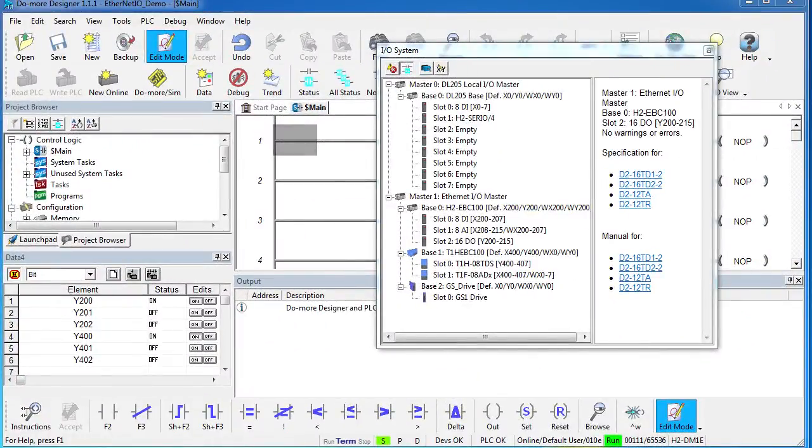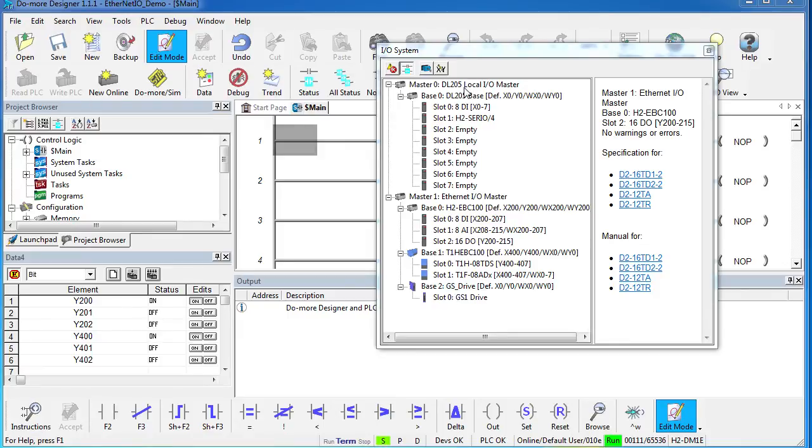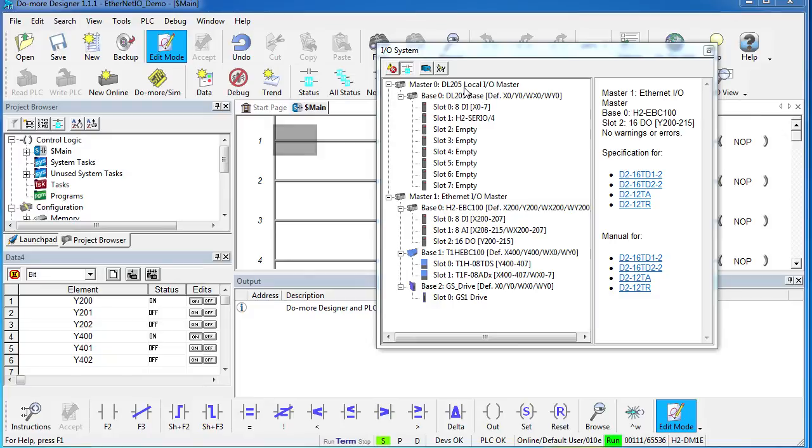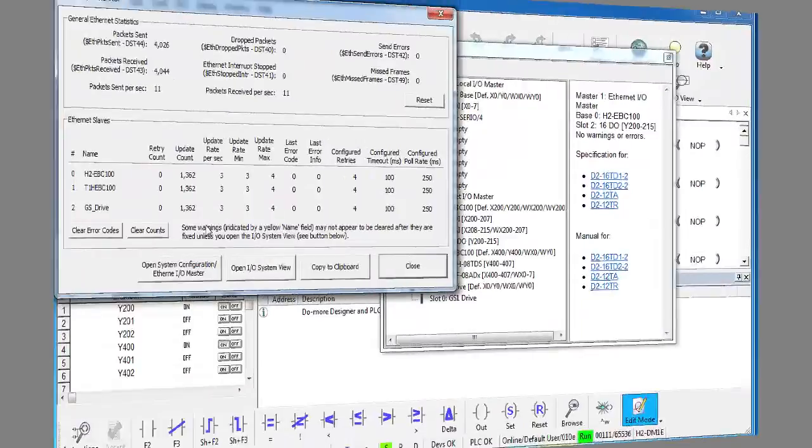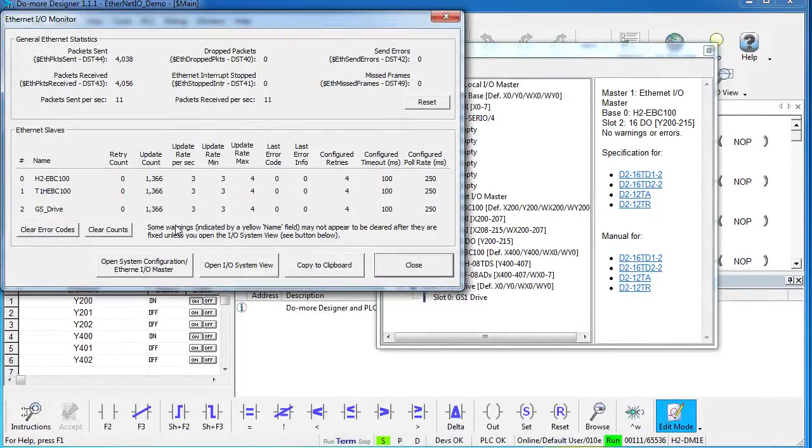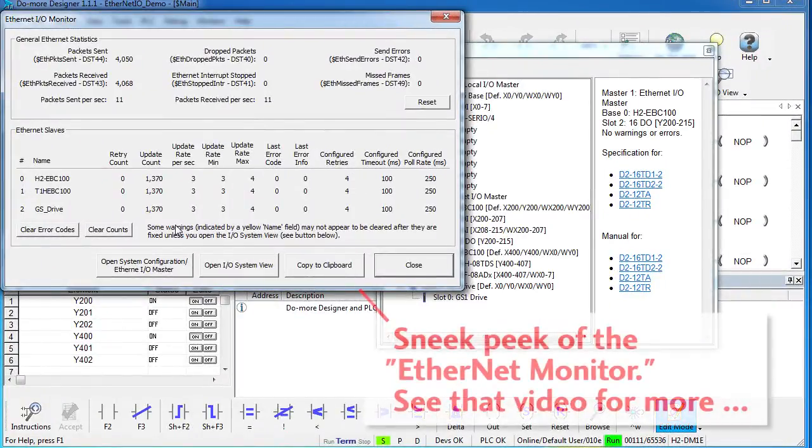And the best part of all this Ethernet I.O. stuff is that the configuration for all these slave devices is stored in the Do-More. So if you swap out any module anywhere in the entire Ethernet I.O. network, you don't have to manually reconfigure it or write any ladder code to initialize it. Just drop it in and the Do-More automatically configures that module for you. That ought to be enough to get you started with the Ethernet I.O. on the Do-More.